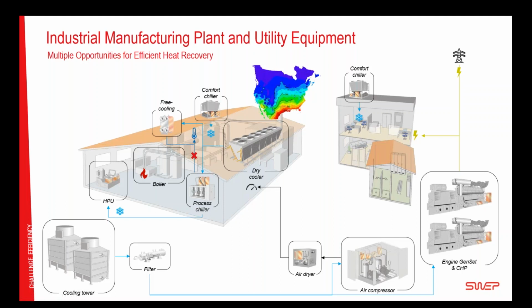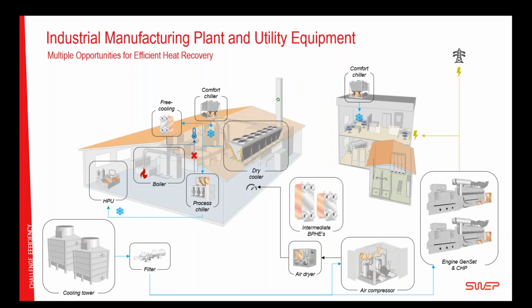What you want to do then is to separate the outdoor system from the indoor process, because the indoor process can be very sensitive, and you want to increase the redundancy of separation. And there, a brazed plate heat exchanger is a very efficient tool, being compact, cost efficient, and highly thermally efficient. We will look into that a little bit later in detail. Let's continue to build here.